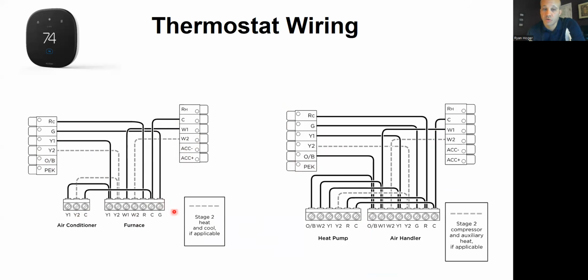And then from the indoor equipment, meaning the furnace, air handler, or fan coil, to the outdoor equipment, meaning AC or heat pump, an AC would be 2 wires. A heat pump would typically need 5 wires going outside. So typically you almost always have to pull new wire from the outdoor unit to the indoor unit, and sometimes from the thermostat to the indoor unit. Now the dotted lines, as we mentioned last time, mean you have additional stages. So if you're going to multi-stage equipment, you might need even more wires there.